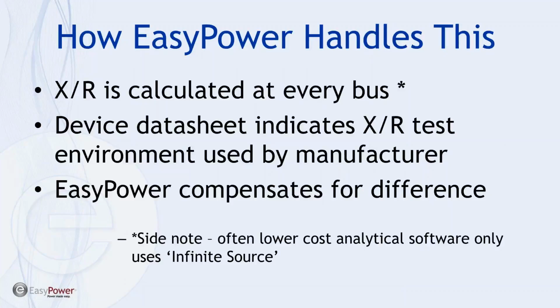And just a side note, as you can imagine, this is a fairly heavy-duty computation load. When you calculate X over R at literally every bus in the system, and because it's all interactive at each fault, there's some need to be fairly rigorous. That's one of the things that sets aside, if you will, less costly analytical software, because they handle this discussion only at one data point for the utility.